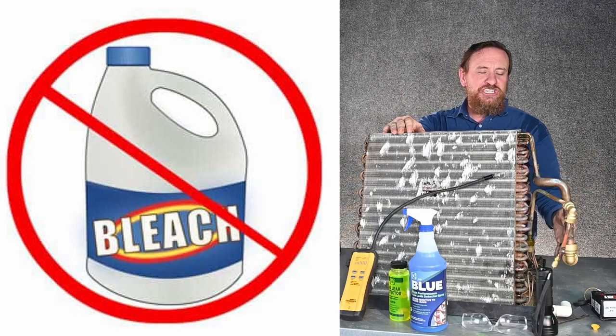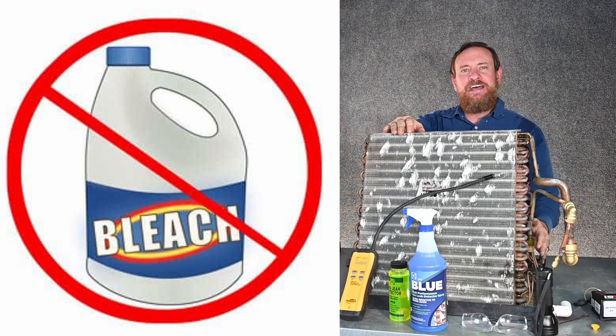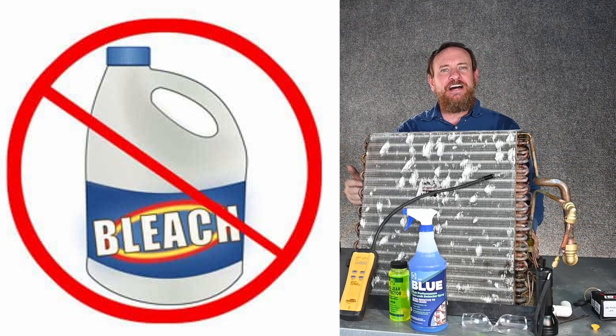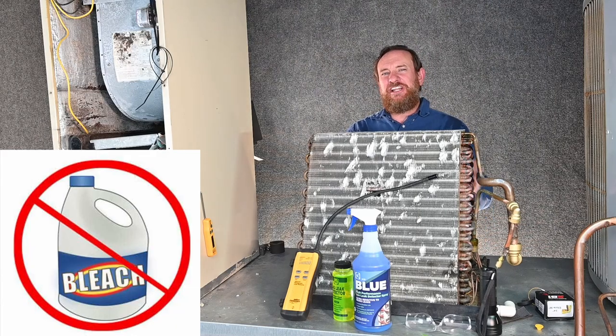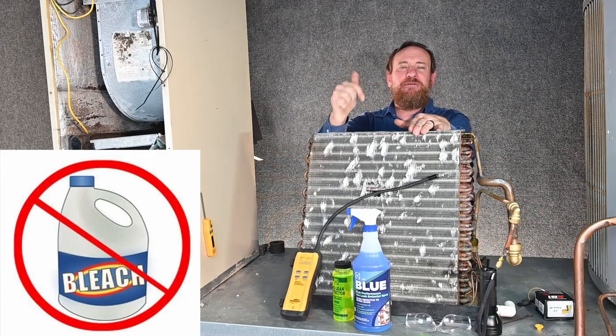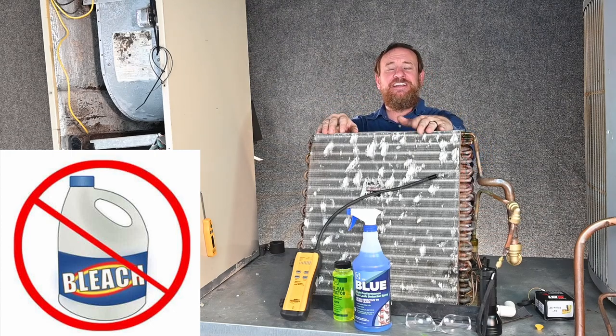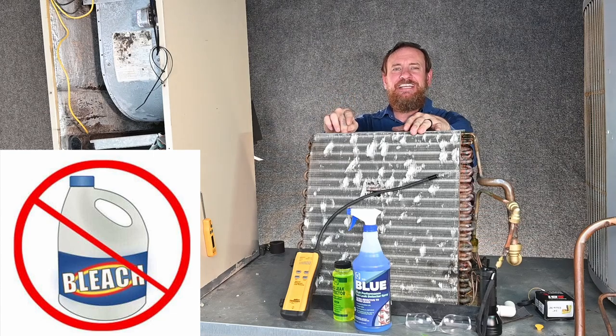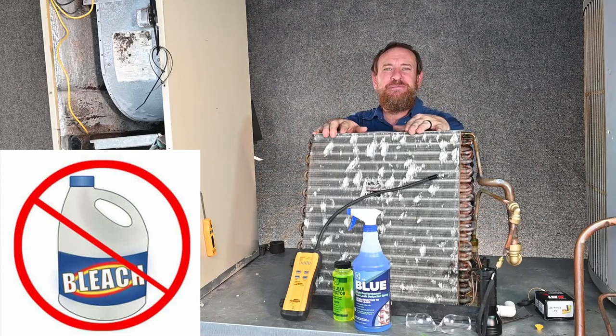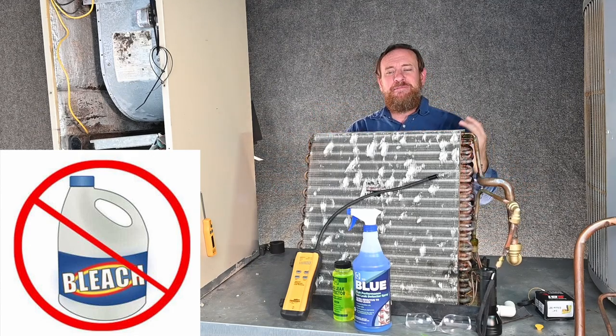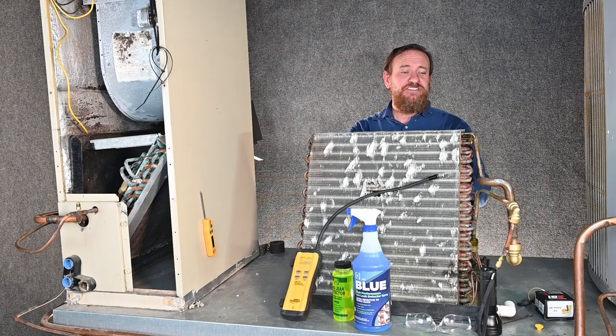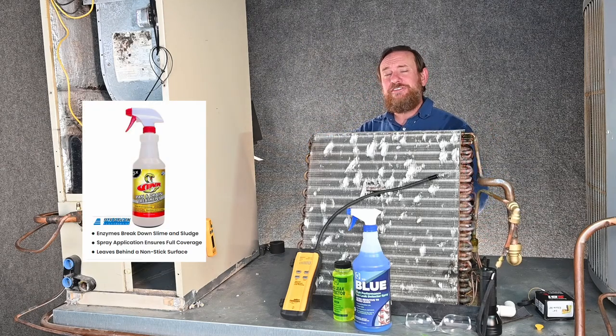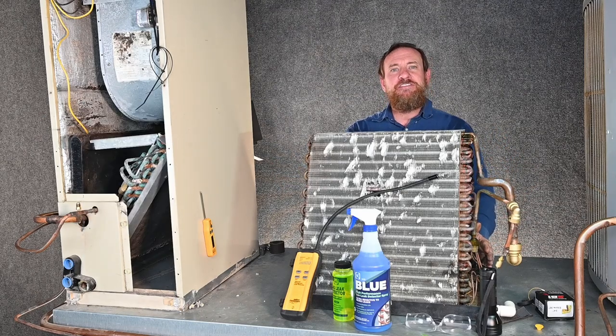Bleach is very corrosive. Even pouring it into the drain line means those vapors can come back up into the evaporator coil — and now you have copper, aluminum, galvanized metal, water, and bleach together. That bleach starts eating away the evaporator coil. When I go to a customer's house and smell bleach, there's a much higher chance it's going to be low on refrigerant. Please don't recommend customers put bleach in their unit — there are proper products made to clean drain lines.